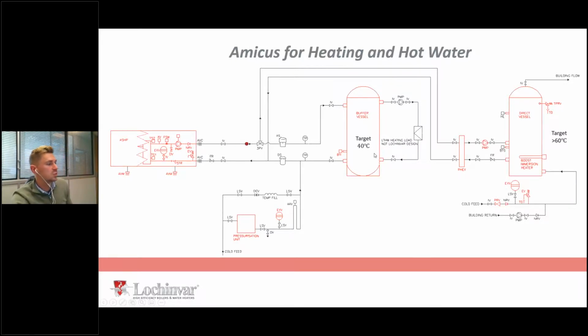So under normal circumstances, what you do is you flow into a thermal store, you get your 40 degrees in your thermal store, and the secondary side of your heating system flows off and does whatever it needs to do to serve that heating load, underfloor, whatever it may be. That'll give you a heating system running at 40 degrees of something like 400% efficient, which is massive, because we've reduced the amount of work the air source heat pump needs to do. We're flowing at the temperature we need for the system, which is going to be 42 to generate 40, right? Because we've got that 5-degree delta T and we want to flow in at 42 and return at 37. Then what it will do is it will monitor your BTS, which is your hot water sensor.